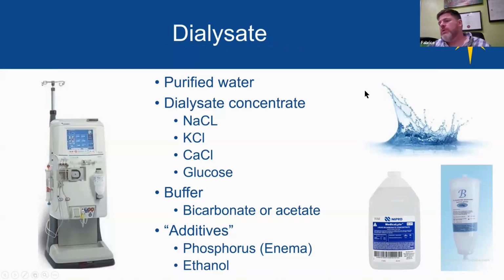Just a few words on the dialysate. If you use, for example, the Prismax or the Prismaflex, it just comes with bags. So you don't have a lot of flexibility with what you are doing with your dialysate. With the Phoenix machine, it's here on the picture, you have a source of purified water. So we have our water unit, and that gives us purified water. Then you have acid concentrate, and then you have bicarb.